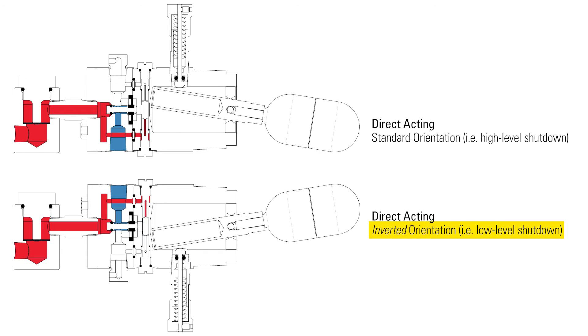If you are installing it for a low level shutdown, you will want to install it upside down with the button on the bottom and keep it in the direct acting mode. This will keep the test button functional and allow the switch to signal a valve only when the level gets low enough for the float to drop.